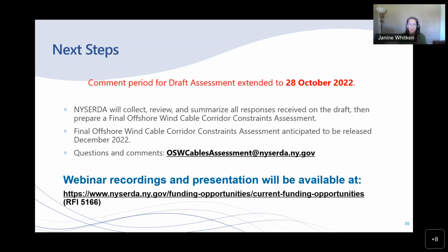Janine, if I may offer, we did consider the concept of installing multiple cables at the same time by the same installer or the same developer, if that's feasible. It would potentially allow for tighter spacing logistically, because you know exactly where the cables are being buried at the same time. So there could be some efficiencies in terms of spacing to group those cables somewhat closer together, rather than sequential installation, where you have to allow a little more room for error and for the unknown of identifying the location of cable that's already installed.